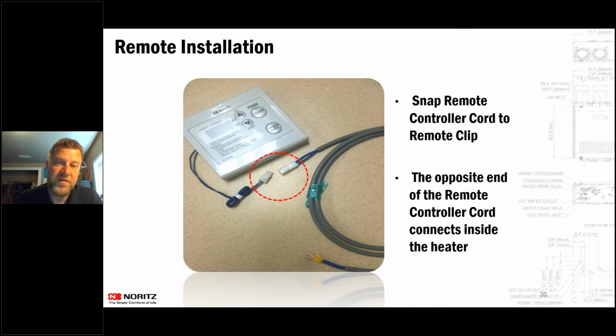I always recommend that you put it on the side of the unit or on the wall, not on the front of the unit, because that controller is also your diagnostic tool. If you ever have to work on that unit and you take the cover off, your diagnostic tool just went with the cover. So I always recommend the side or the wall. You can put it on the front, you can do whatever you want, but typically when I'm going out to a unit, I have to diagnose it, so I like to have it in a place that makes it as easy as possible.